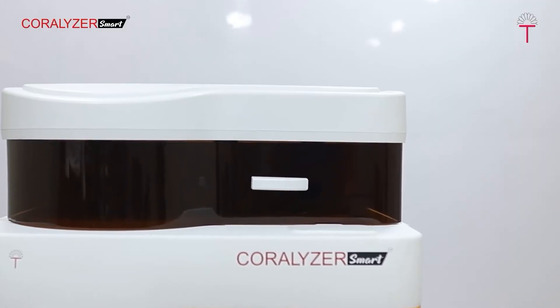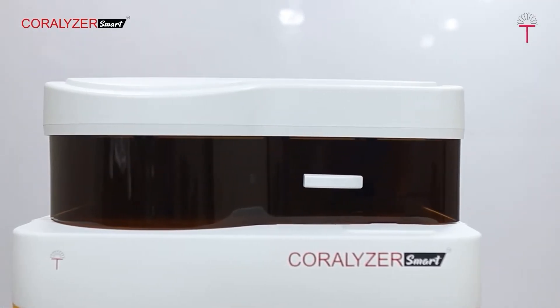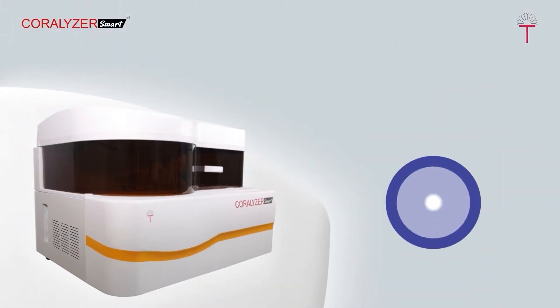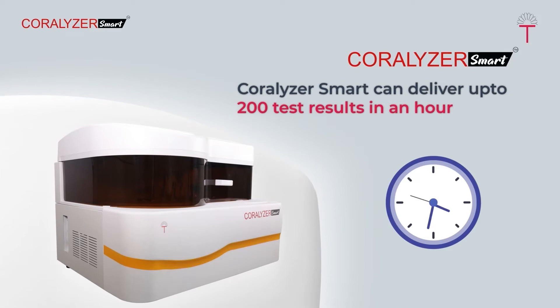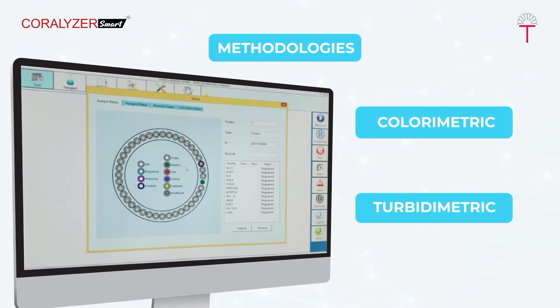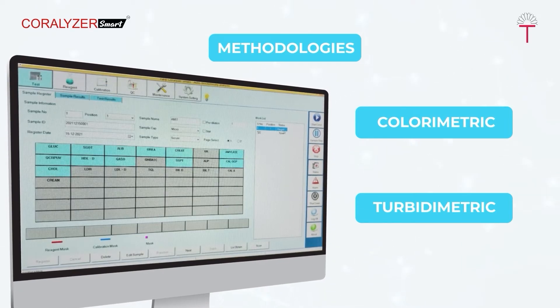Coralyzer Smart is equipped to handle multiple chemistries loaded at a time and deliver reports of different chemistry or turbidimetric results simultaneously. It can deliver up to 200 test results in an hour, making it efficient and convenient for various test profiles. Coralyzer Smart can work on both methodologies — colorimetric as well as turbidimetric — thus avoiding the need for another dedicated analyzer for turbidimetric tests.